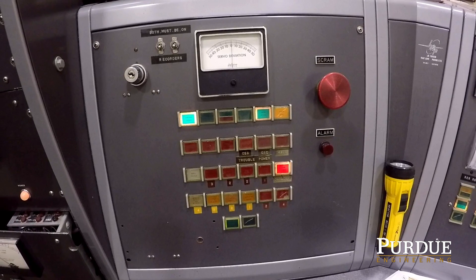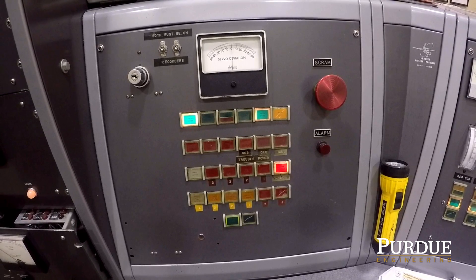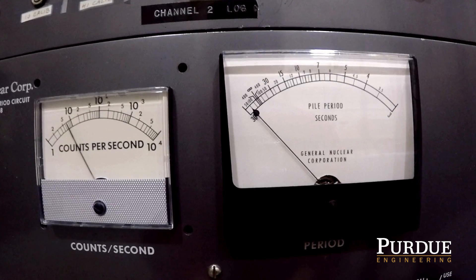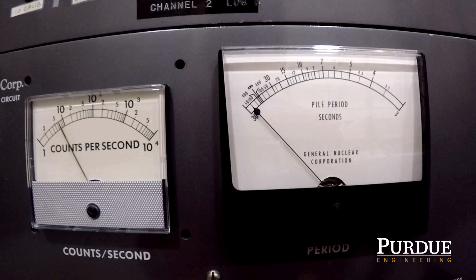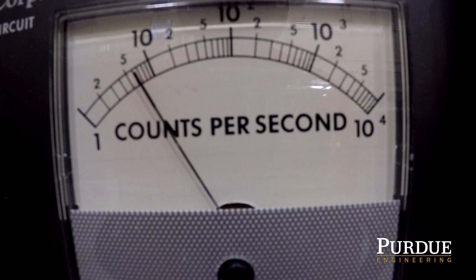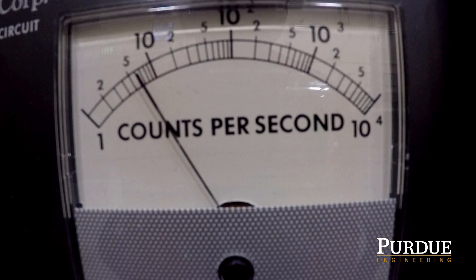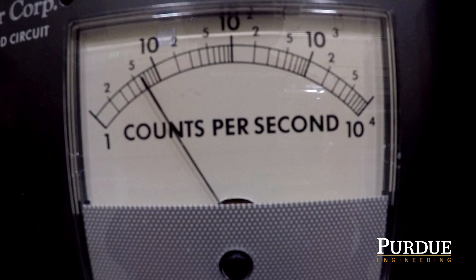If there is a reactor shutdown, one or more of the tiles will indicate the cause of the shutdown. When the reactor is starting up, operators reference channel 1 to see the counts from a special detector called a fission chamber. The fission chamber shows from 1 to 10,000 counts per second and also feeds a log power period circuit.